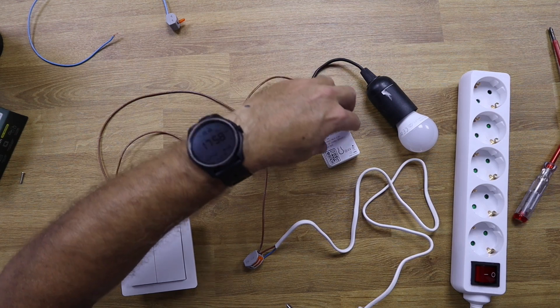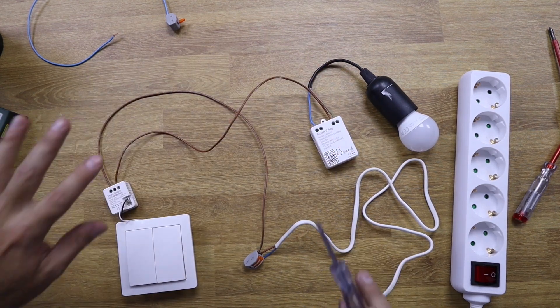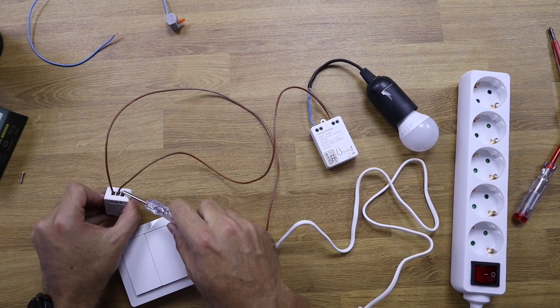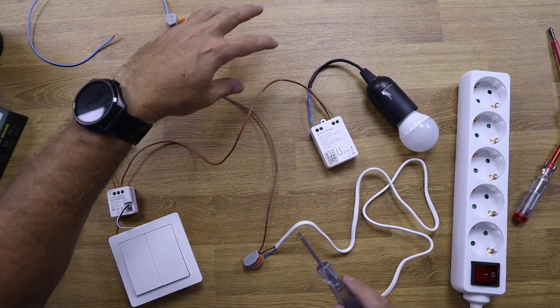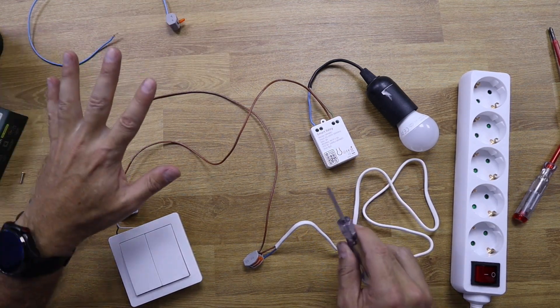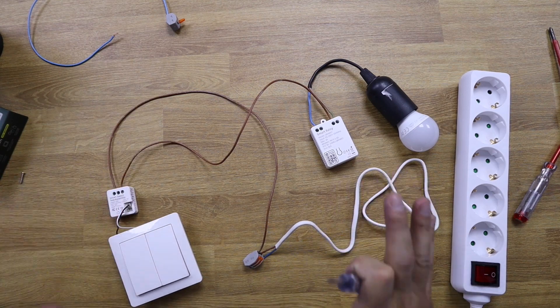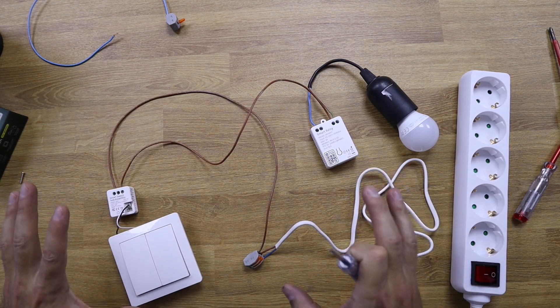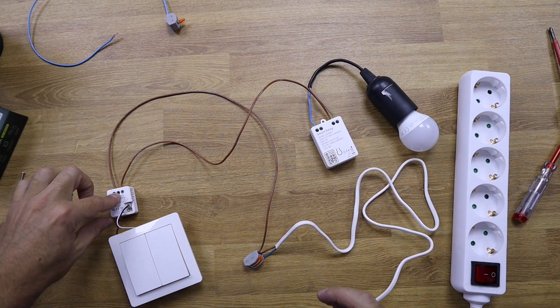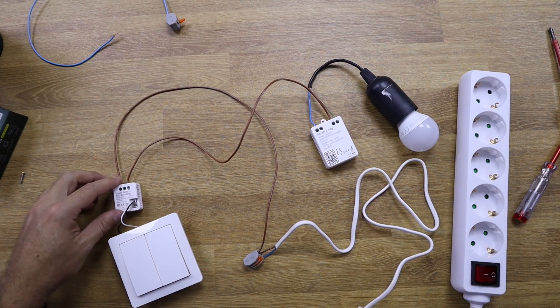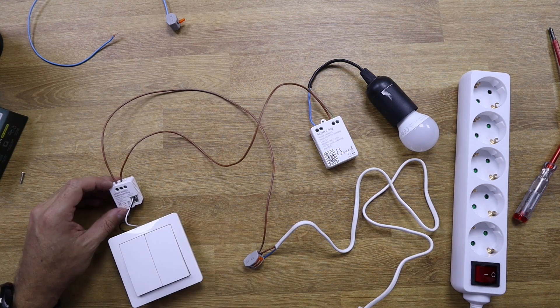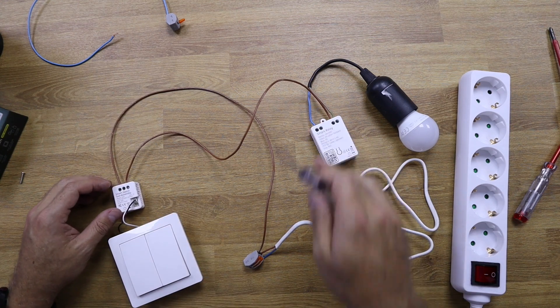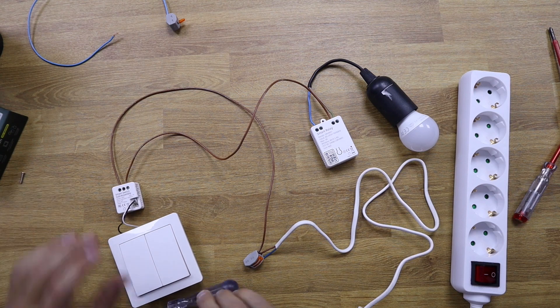Of course, if we have a second unit, it will come out from the L2 and go to the other switch that we have to control another set of lamps. Right over here, we just need one more connection, which is the neutral input. The sub-switch will not use any neutral, just live and then the outputs for L1 and L2, but the main switch will require a neutral input.